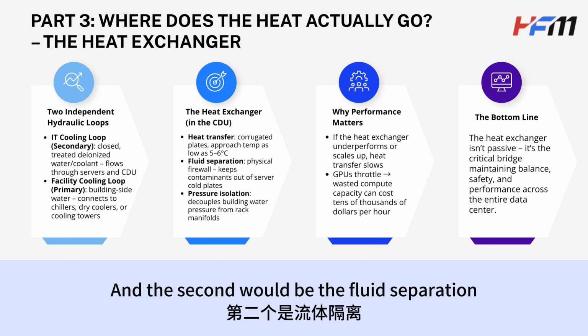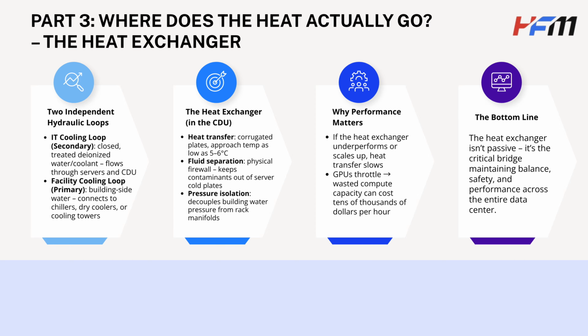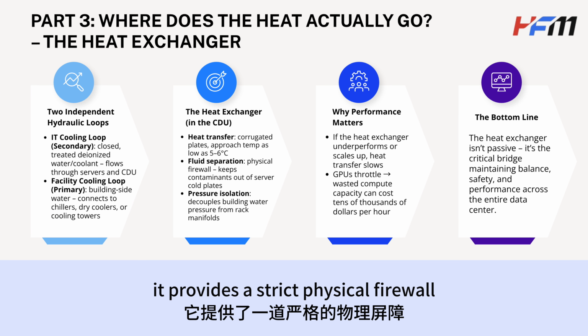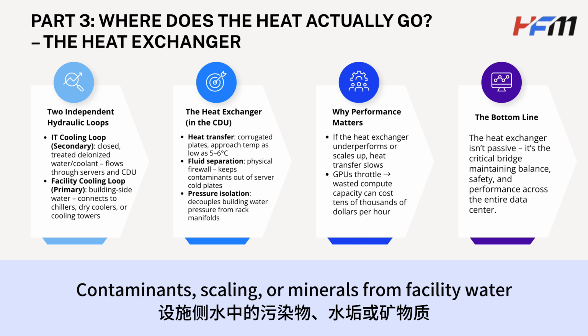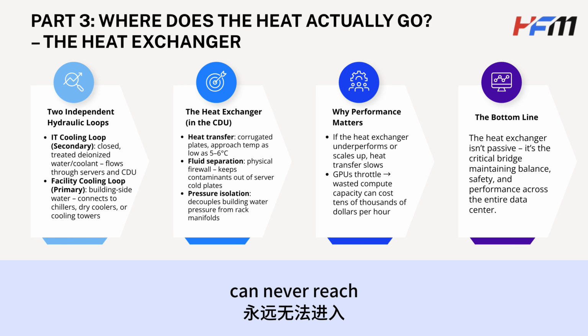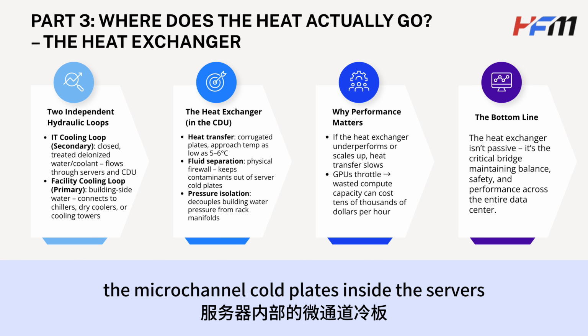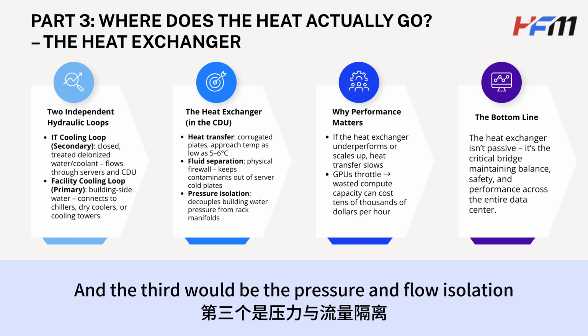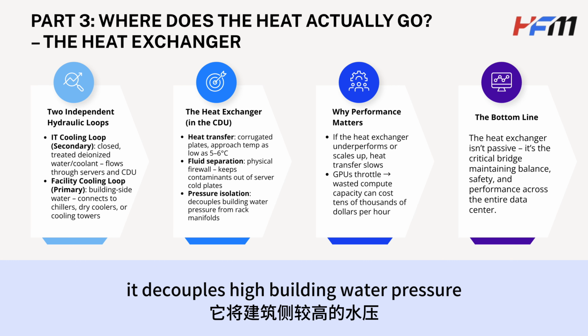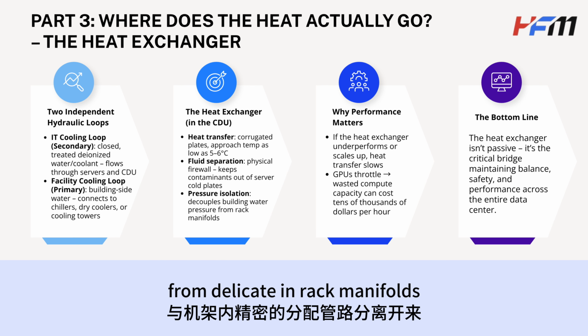The second is fluid separation. It provides a strict physical firewall—contaminants, scaling, or minerals from the facility water can never reach the microchannel cold plates inside the servers. The third is pressure and flow isolation. It decouples high building water pressure from delicate in-rack manifolds.